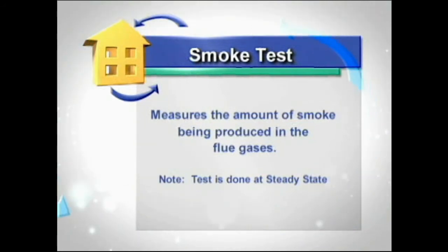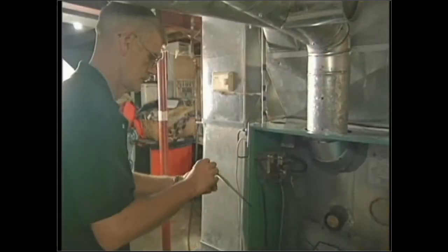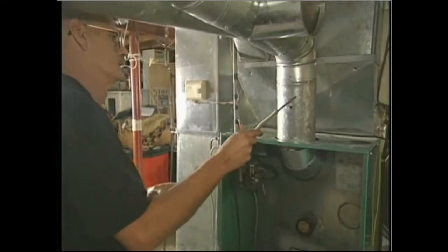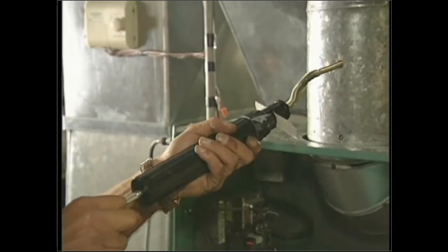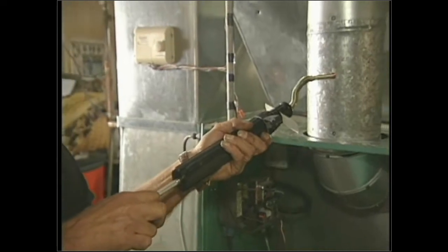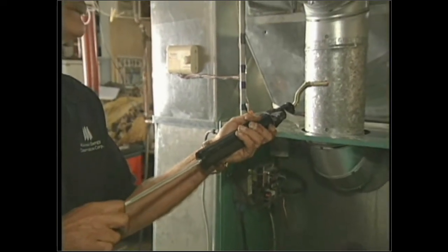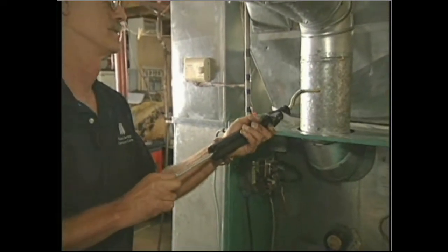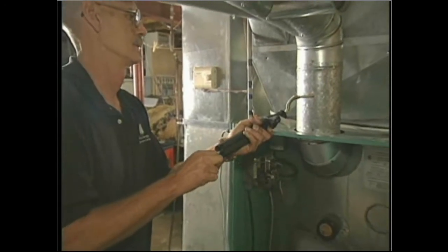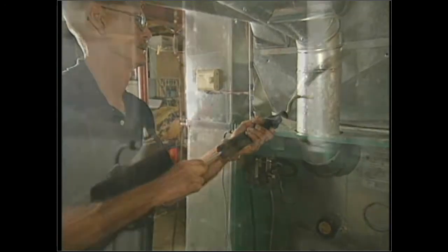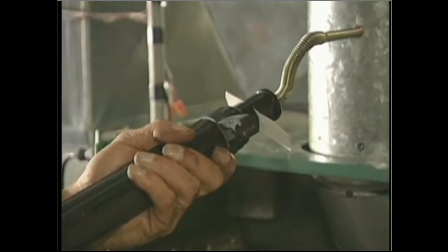And then what type of equipment are you using? We use a pull tester. It's a very simple piece of equipment. We take a piece of special paper, we put it inside here, we take this probe, we stick it into the same hole where we did the draft test. We do 10 slow, long pulls. Okay, without removing that probe, you're just simply, like a bicycle pump almost, just pulling it out. Just a hair slower. And that's actually sampling that? Yep, it's pulling an air sample through here.